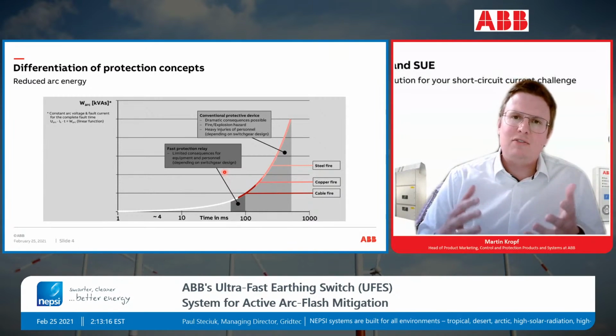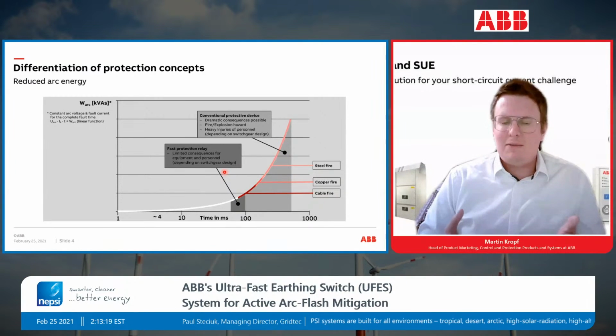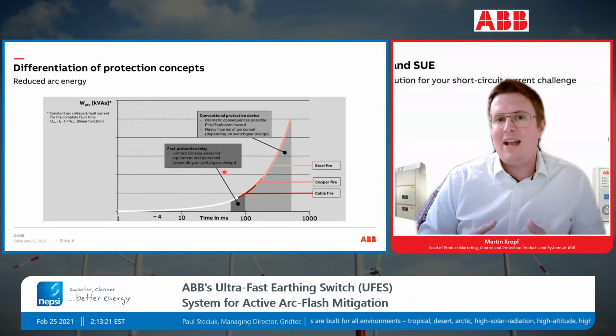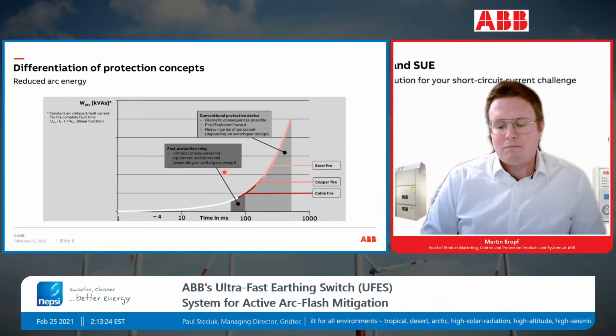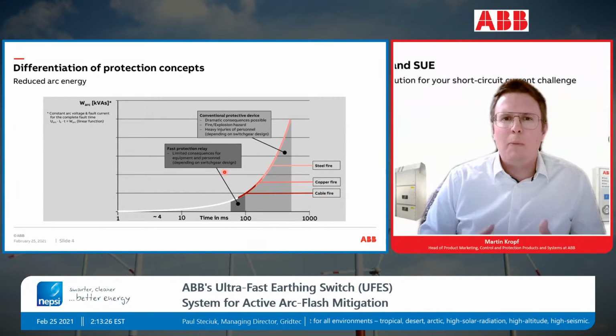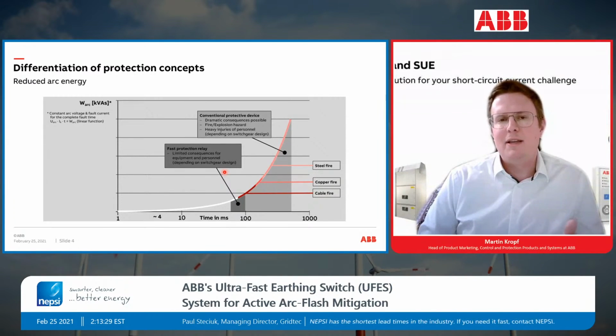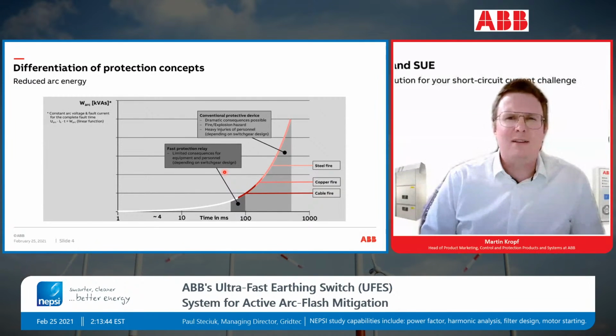I mean, it is fulfilling its need today. It's highly standardized as well, and so it's not that easy to optimize that breaker, because it's always a payoff. I mean, you can make it faster, but a breaker today, 50 to 80 milliseconds opening time, roughly, a medium voltage breaker. So to bring this really down, it's really hard, and it will affect the performance of the breaker. It would then not operate, let's say, 10,000 times maintenance free. So we will not be able to change the breaker because this is widely used and accepted technology.